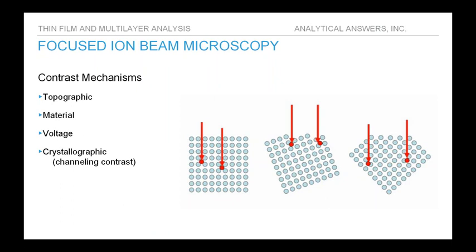The third contrast mechanism is voltage contrast, which is a change in secondary electron intensity based on local differences in surface potential caused by local differences in surface conductivity. We try to avoid this by coating samples with a very thin layer of conductive material, as is done in SEM analyses. However, voltage contrast is a very important tool for fault isolation in microelectronics, for instance by localizing the region of opens in circuit traces.